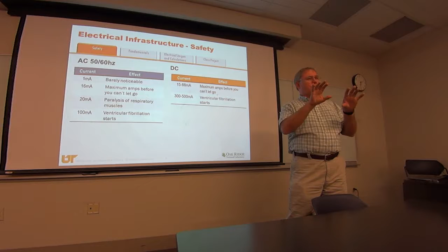But anyway, how many of you have GFCIs in your restrooms and bathrooms? Do you know what current those things trip off at? Let's say you're in a bathtub and somebody throws a radio in there and says, hey, watch this. The GFCI will trip, but do you know what amperage it trips at? 6 milliamps, and it trips almost instantaneously. So all you feel is a little boop, and that's why you have them in the bathroom. If you get in water with electricity on it, it'll trip the thing off immediately.